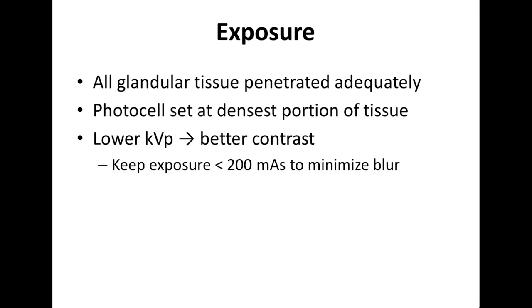During mammography, four factors are very important: exposure, compression, position of the breast, and mammographic views. Regarding exposure, the goal is that all glandular tissue must be adequately penetrated. We achieve this by placing the photocell at the denser portion of the tissue. We also keep the peak kilovoltage lower to get better contrast, and we keep the exposure less than 200 milliampere-seconds to minimize blur.